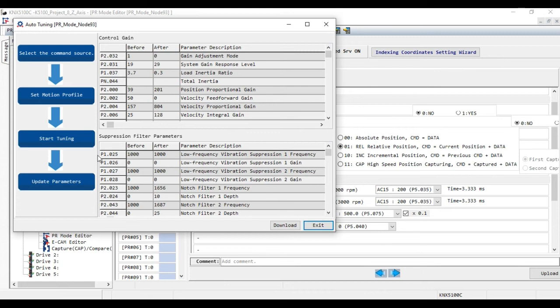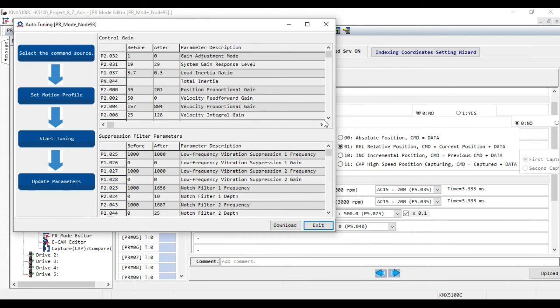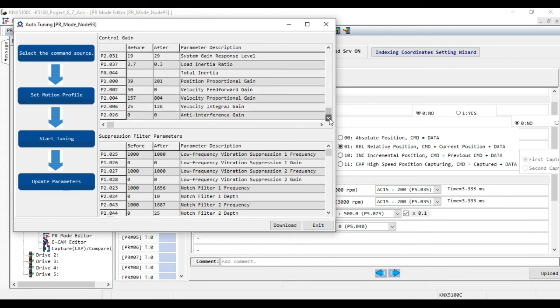Here you can see the before and after values of all those parameters like gain adjustment mode, system gain response level, load inertia, total inertia, position proportional gain, and all parameters are given there. So in the end, you have to click on Download and your tuning process is completed. Thank you.